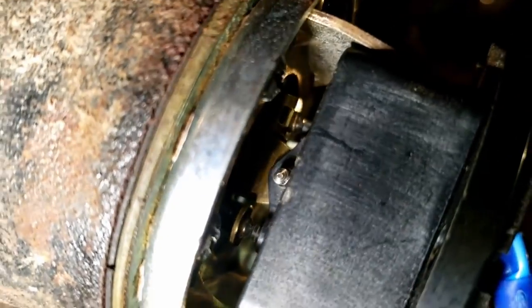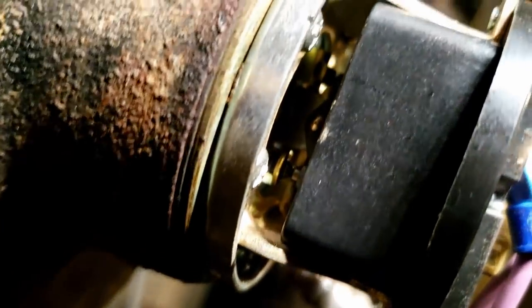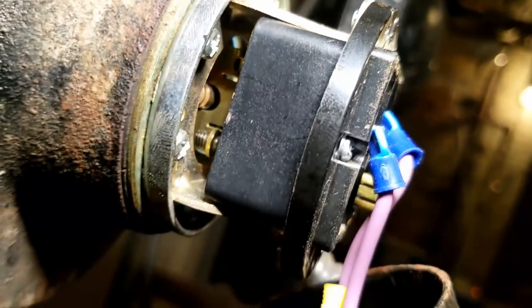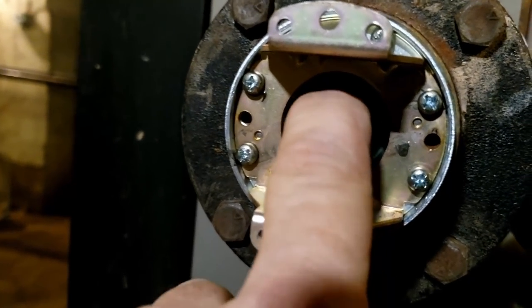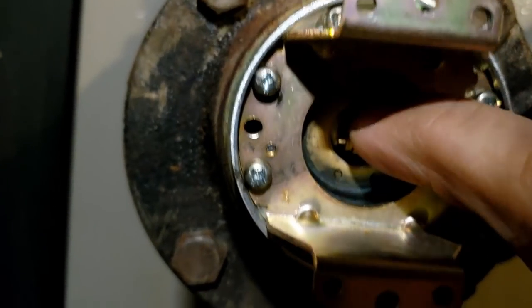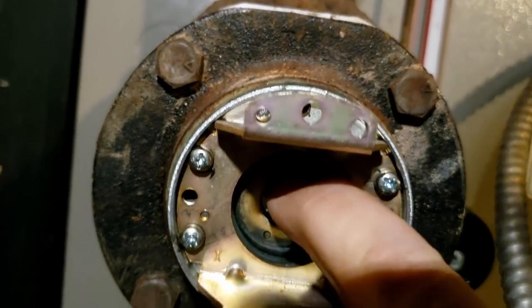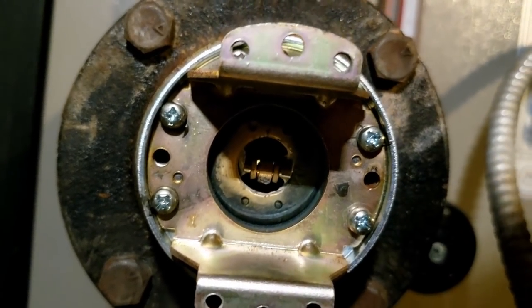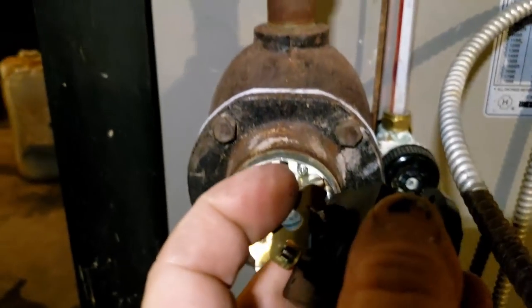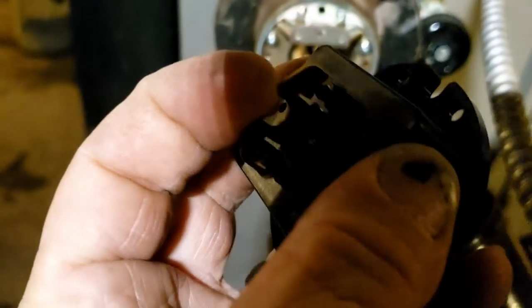Got all that marked. Let's go ahead and take that switch apart, take a look in there. And all that is - you can kind of see in there, switch mechanisms right there. You can kind of see, so you can see there's a little roller. That's the float. The float goes up and down pretty easy. That's the ball float in there, so we know that's not getting stuck on nothing. That's a nice little check you could do, so we know it's not getting stuck.